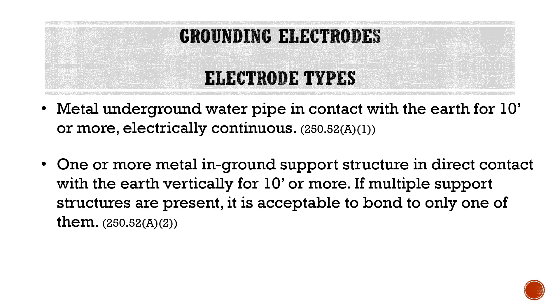A2, our in-ground support structures: one or more metal in-ground support structure in direct contact with the Earth vertically for 10 feet or more. It can't be laying flat; it has to be vertical in the ground. If multiple support structures are present, it is acceptable to bond to only one of them. For example, a large commercial steel-erected building may have multiple steel columns going into the ground — if that's the case, we only need to connect to one of them, because by nature of how a steel building is constructed, they'll all end up connected anyway.